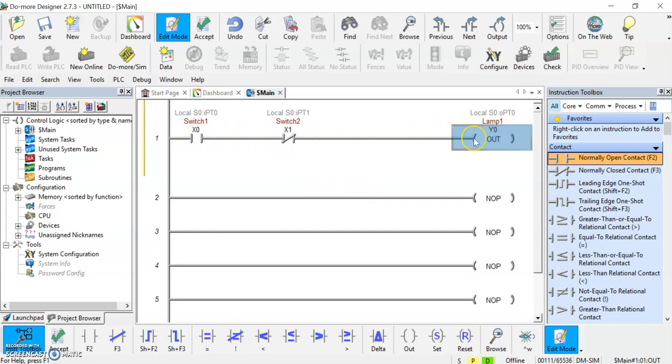We're going to call this lamp 1 and we're going to associate that with a physical point on the actual PLC. Those are used, letter Y is used for outputs. So we go Y and we'll go Y0 as our first lamp that would light up. Now we have two switches here. This switch has to go to a 1, so it has to close, and this one has to be open in the field before lamp 1 will actually activate.